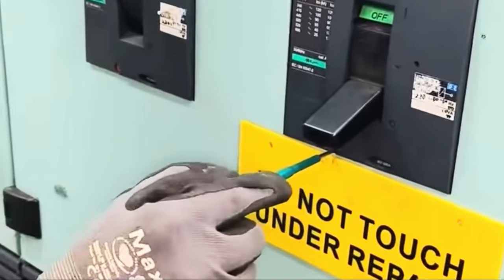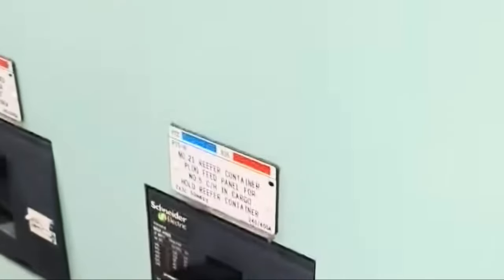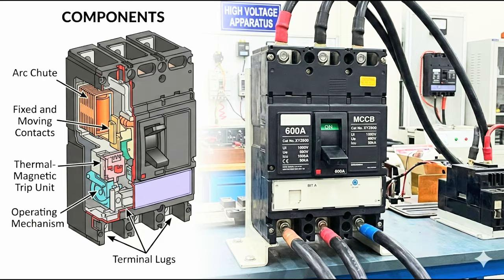Now we try to close the circuit, but it is not closing, because we have not reset it. The breaker has a reset button. It always needs a reset after the breaker trips suddenly, so you need to check the reset again. So we try the connection again. Now it is closed. Now this breaker is working perfectly fine, because it has a UVR mechanism issue where it was stuck with the lever. Now we fixed it, so you can see in the demonstration how we can solve the problem.